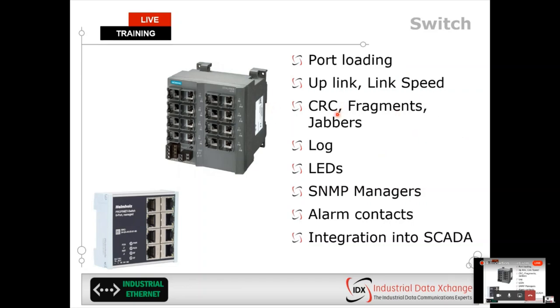Then you have a statistics table, much like the previous slide. The type of statistics useful to you would be things like CRC errors. A CRC error tells me that the telegram has changed somehow, which could be due to faulty wiring, a faulty device interface, electrostatic or magnetic interference, and a host of other problems.